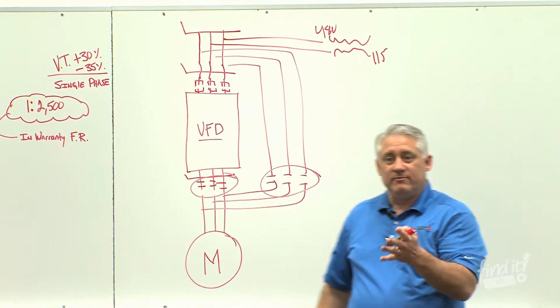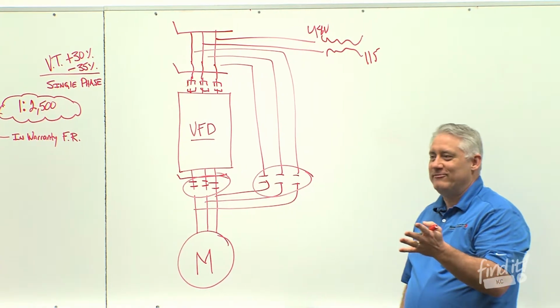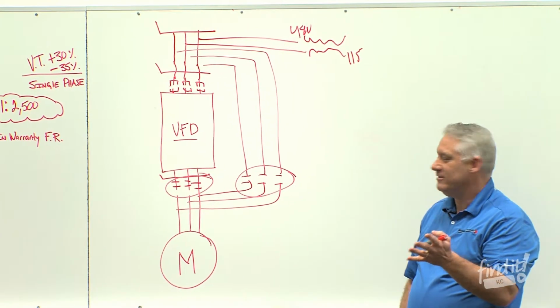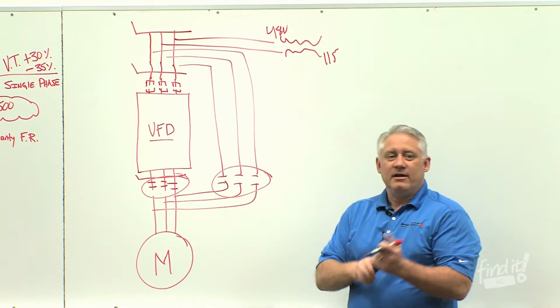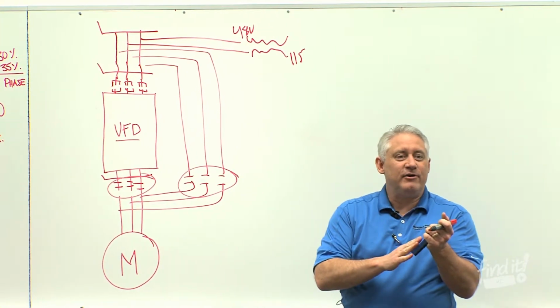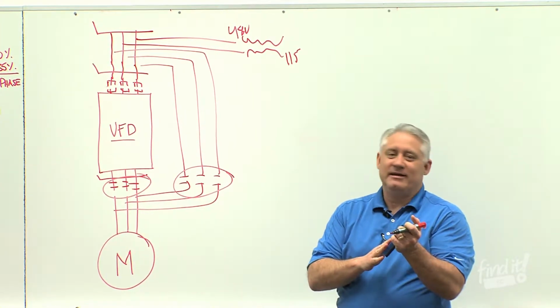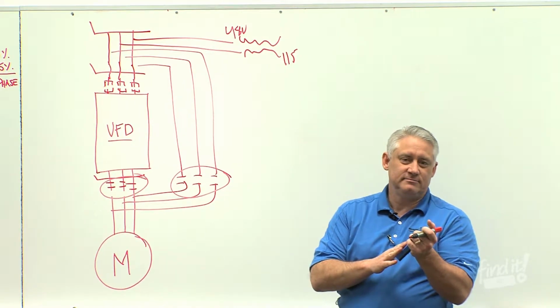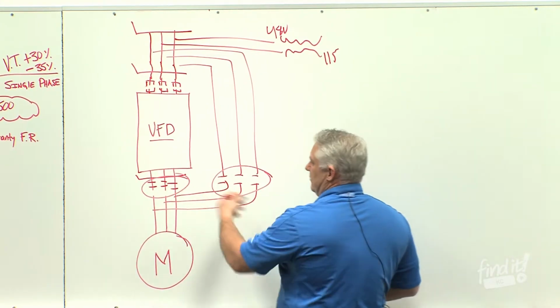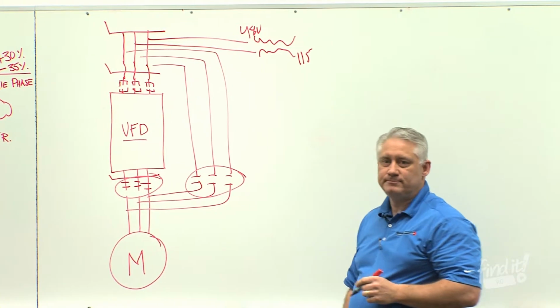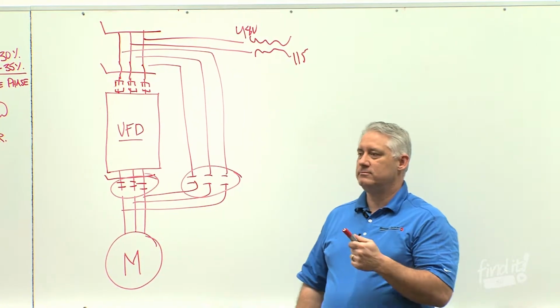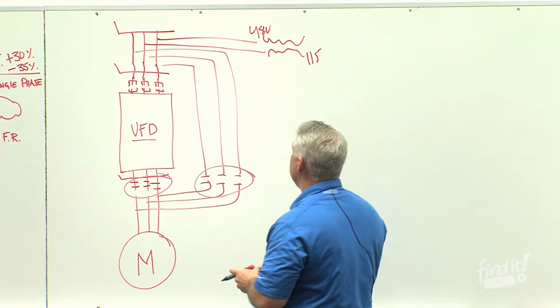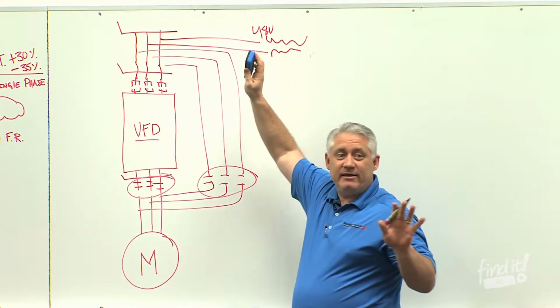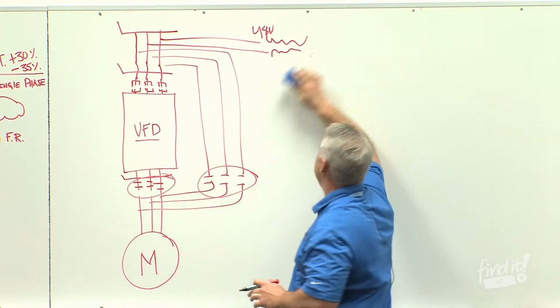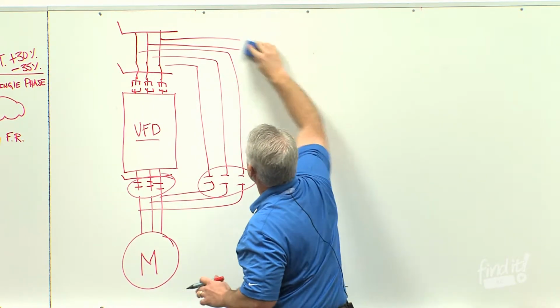But the building management system is saying, no, we need flow. Move the water, move the air. So they pull back in. They drop out and pull back in 150, 200 times in a minute, and it burns up the contactor. Okay, so now we're out there with a service call, changing those out. Any questions on that? Okay, so what do we do about it? Am I going too high level? Am I okay? Okay. So what do we do about it?